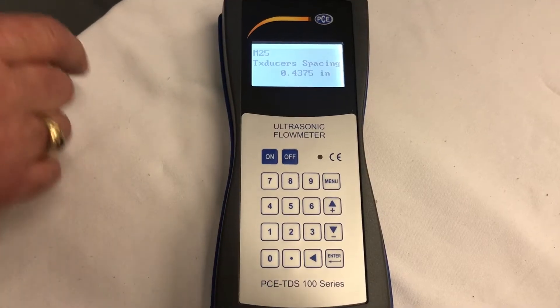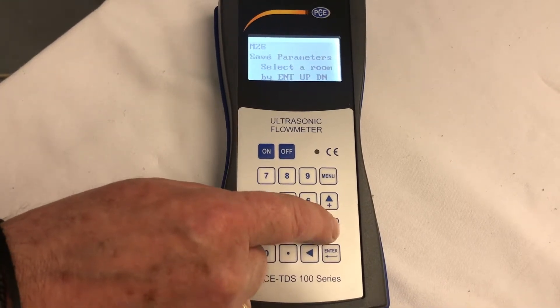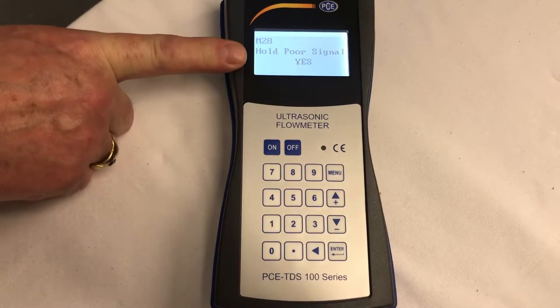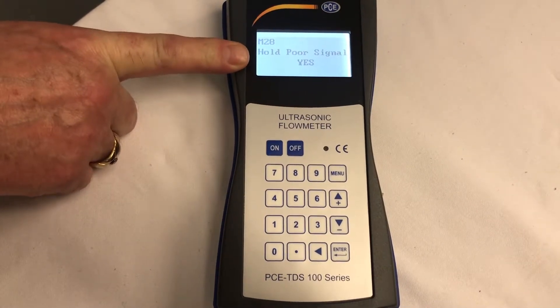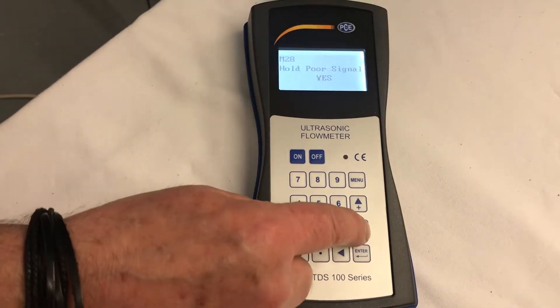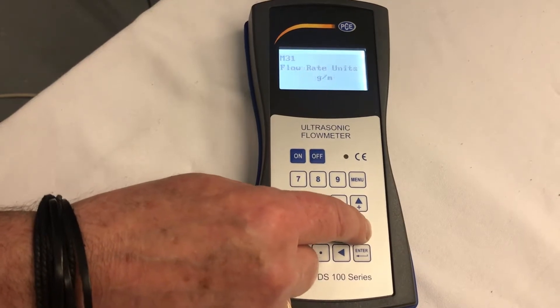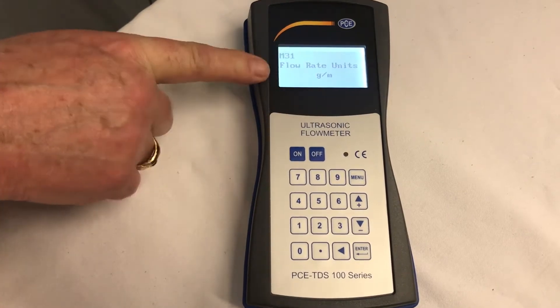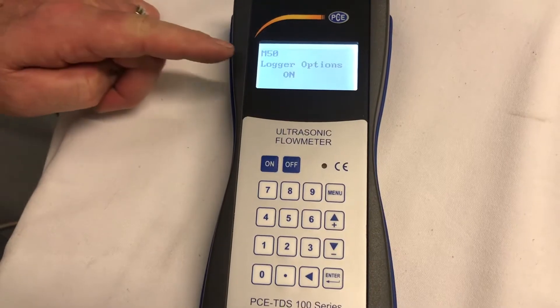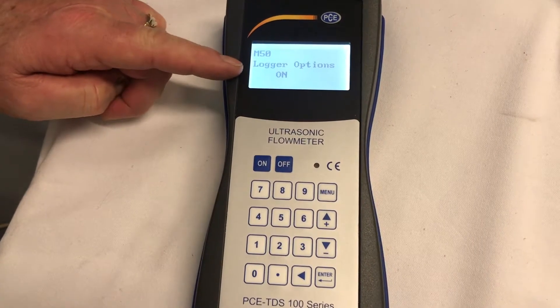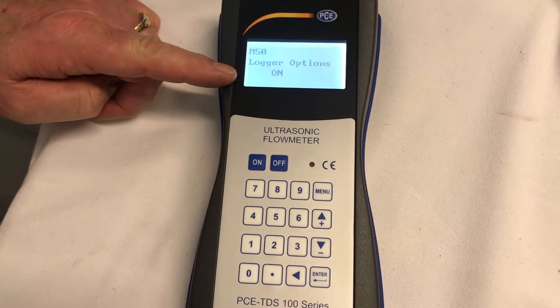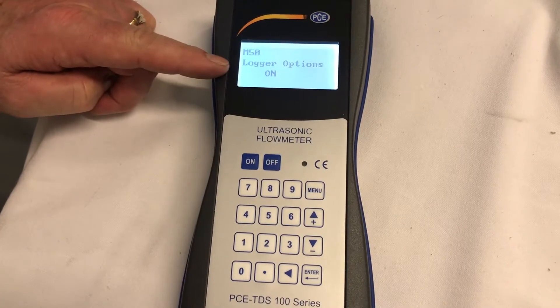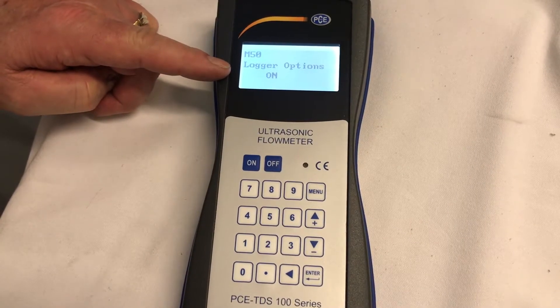Next, we're going to go to M-28, which is for poor signal. M-28. We want to hold the poor signal. Always say yes. After that, we're going to M-31, which is the flow rate. I'm measuring in gallons per minute. Now we're at M-50, logger options on. This is collecting the data from the sensors going into your memory, which is the next step.